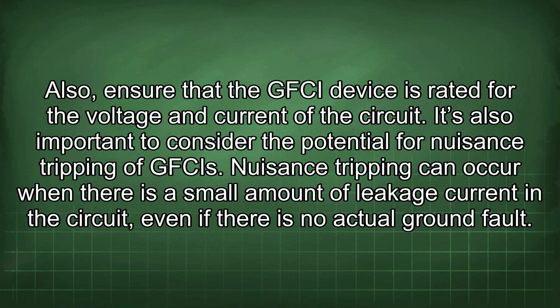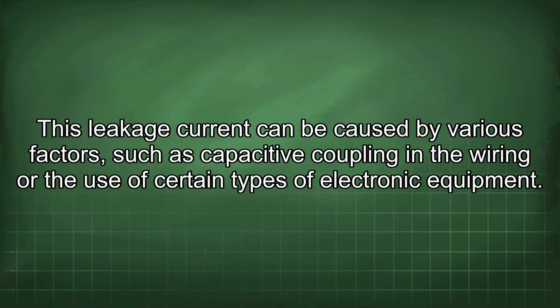It's also important to consider the potential for nuisance tripping of GFCIs. Nuisance tripping can occur when there is a small amount of leakage current in the circuit, even if there is no actual ground fault. This leakage current can be caused by various factors, such as capacitive coupling in the wiring or the use of certain types of electronic equipment.